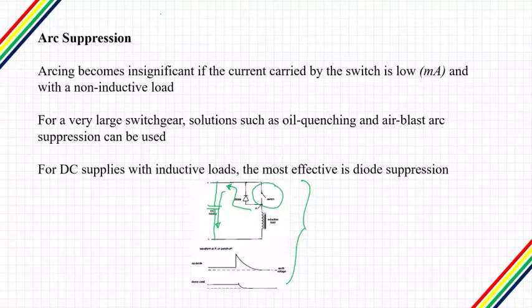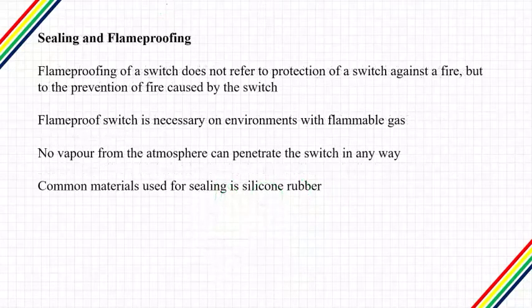Diode protection is much less effective when the circuit operates at a higher voltage — for example 100 volts or more — because the voltage across the contacts cannot be less than the supply voltage, and this is large enough to promote arcing. The arcing will however be considerably less severe than it would be without the diode. Whatever voltage level is used, the diode must be adequately rated both for the voltage and for the current that can flow.